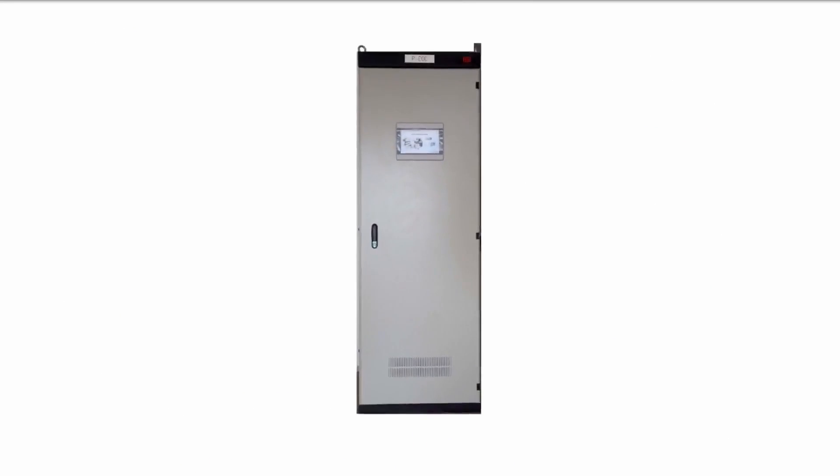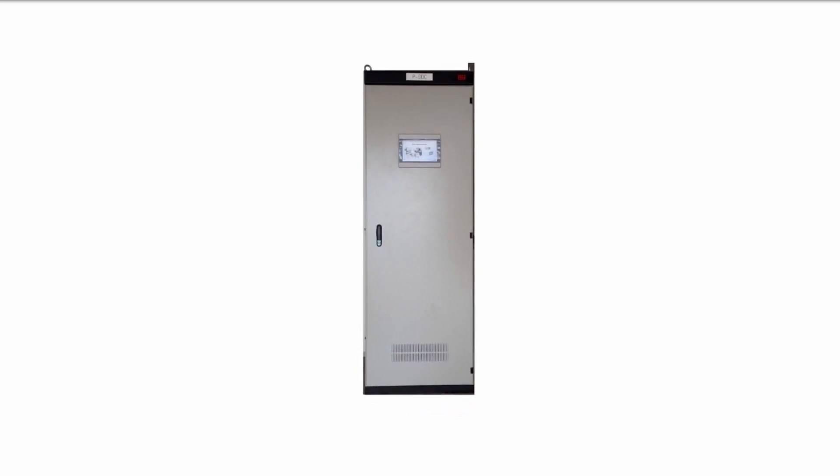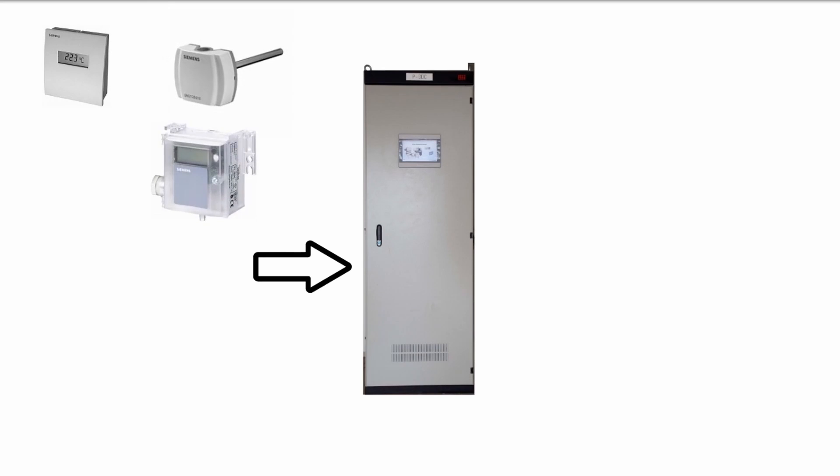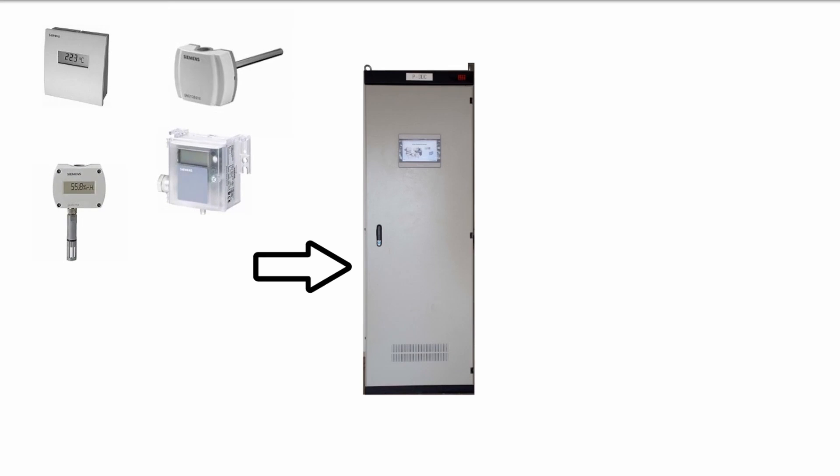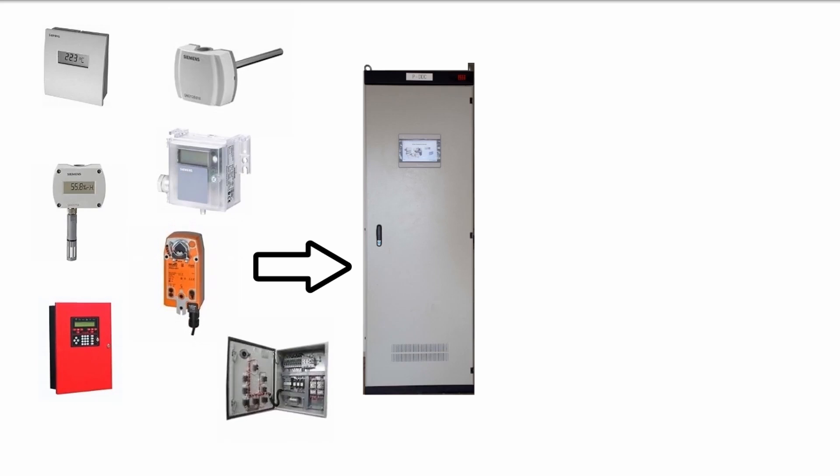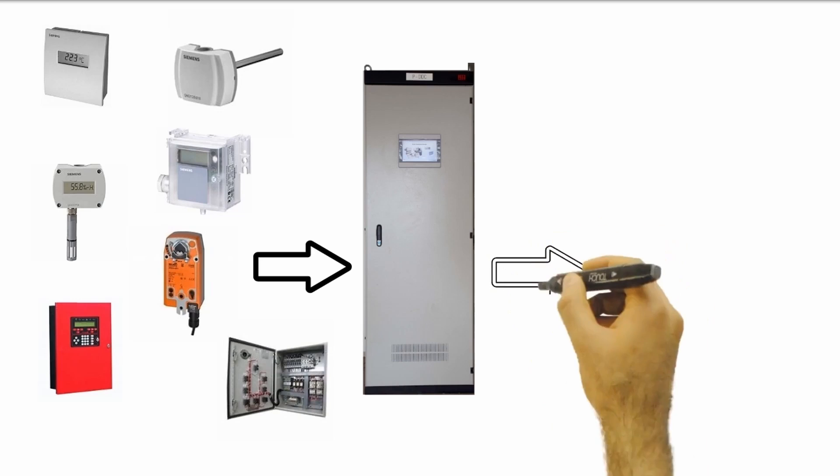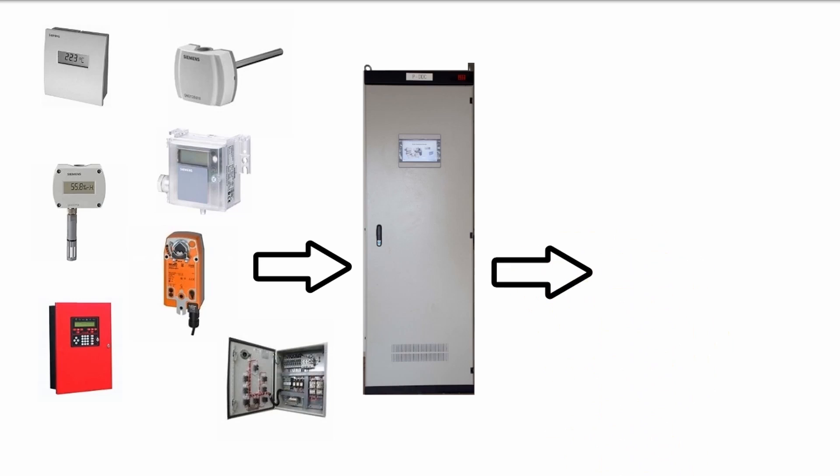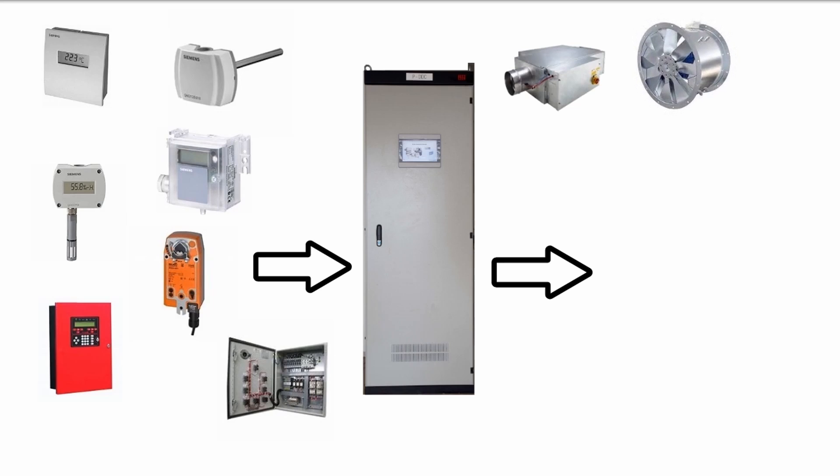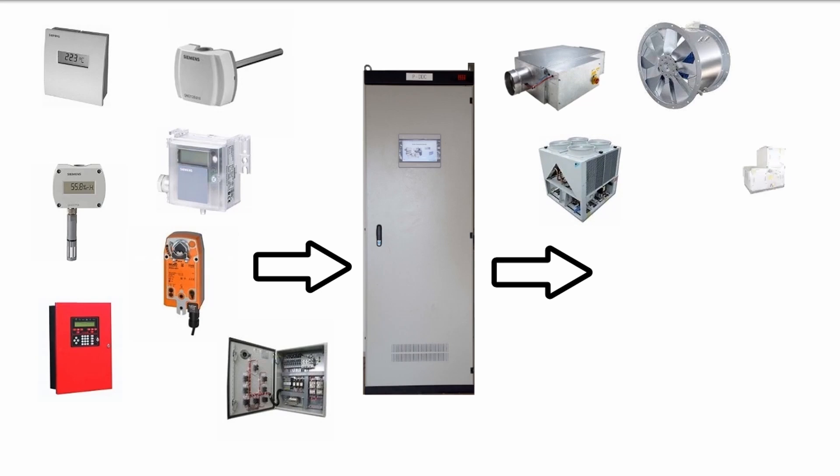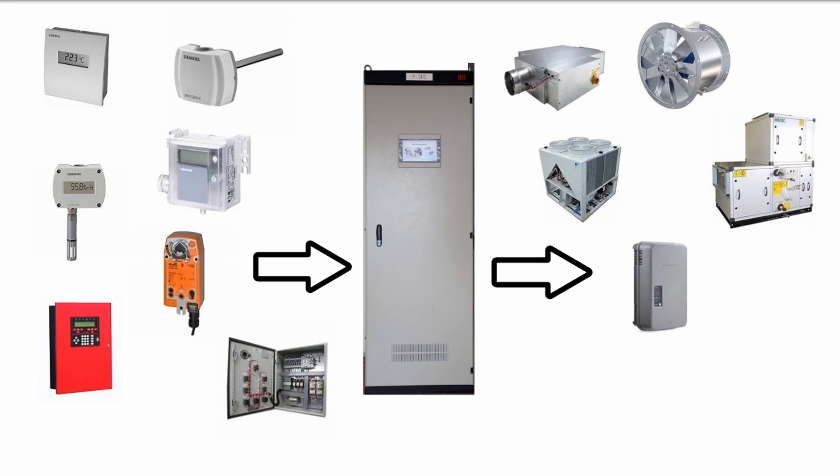In a typical HVAC system, analog inputs to DDC are provided by measuring devices such as room and duct temperature, pressure and humidity sensors. While digital inputs may come from auxiliary contacts from fire alarm control panels, actuators, motor starters, and so forth. On the other hand, analog outputs are produced by the DDC to regulate the opening of a damper of a variable air volume or to control fan speeds among others. While digital outputs are produced to start or stop the condensing units, air handling units, humidifiers, or to open and close dampers or valves.